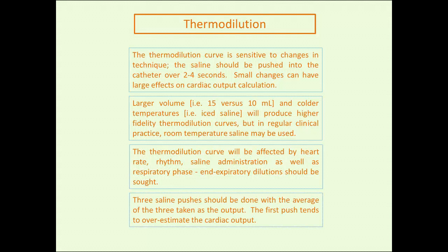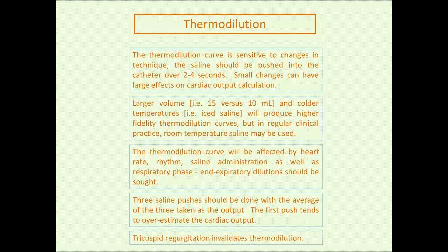It's recommended that three saline pushes be done with the average taken as the output. The first push tends to overestimate the cardiac output. The reason is that the cold saline cools the catheter itself, which has warmed to body temperature. As saline flushes across the warmed catheter, you lose some temperature—so the reading across the thermistor will be lower, producing a lower area under the curve and exaggerating your cardiac output on that first push. Tricuspid regurgitation also invalidates the thermodilution.